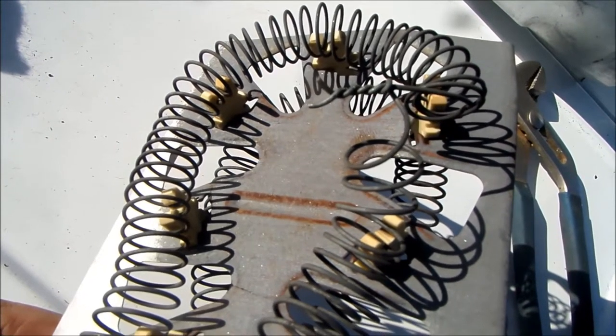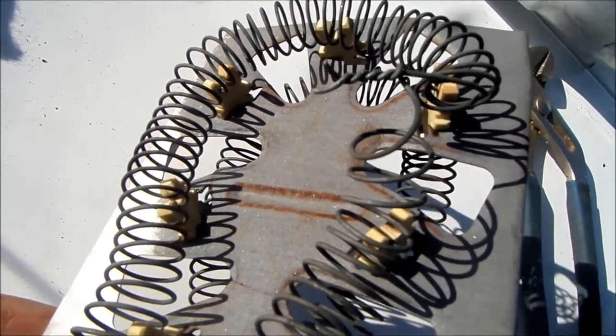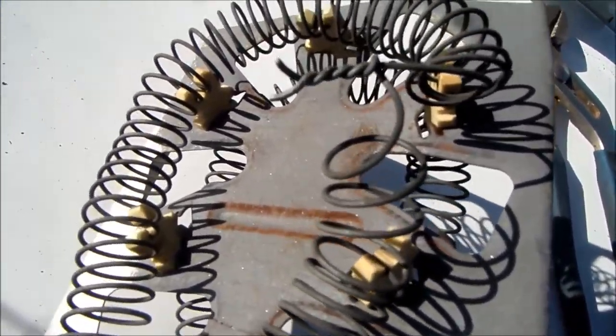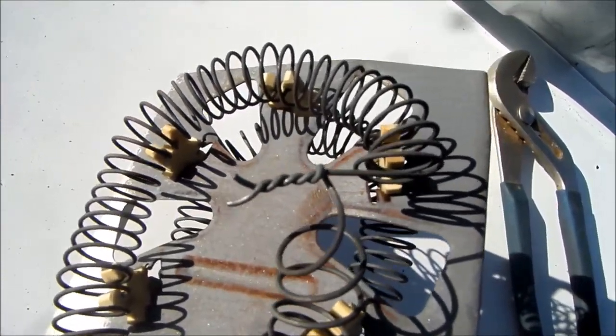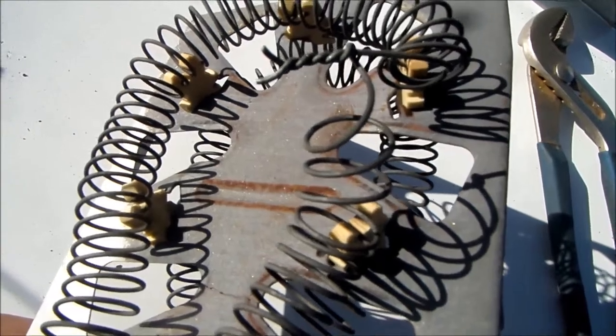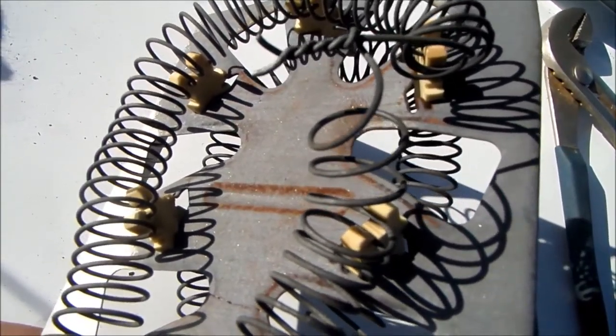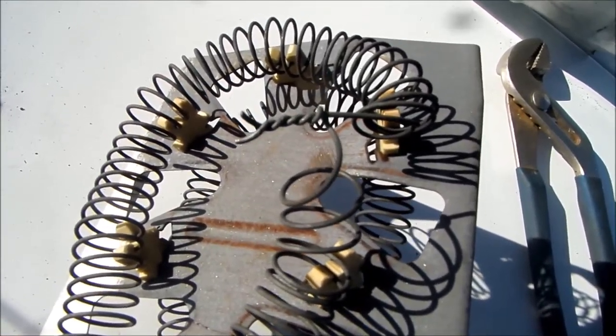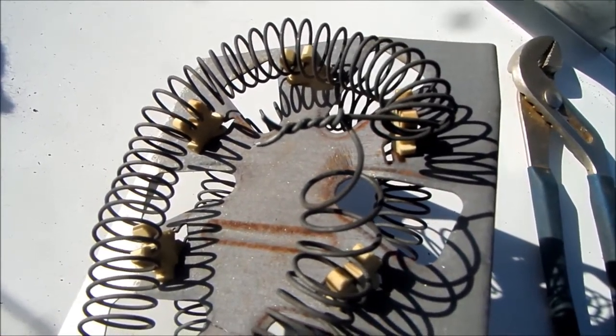Because what happens is if you put too many winds on the tie, it will cause excess heat to build up in that area. So you just want maybe five or six ties, pretty tight. You don't want to go too tight, otherwise you'll break the heat element.